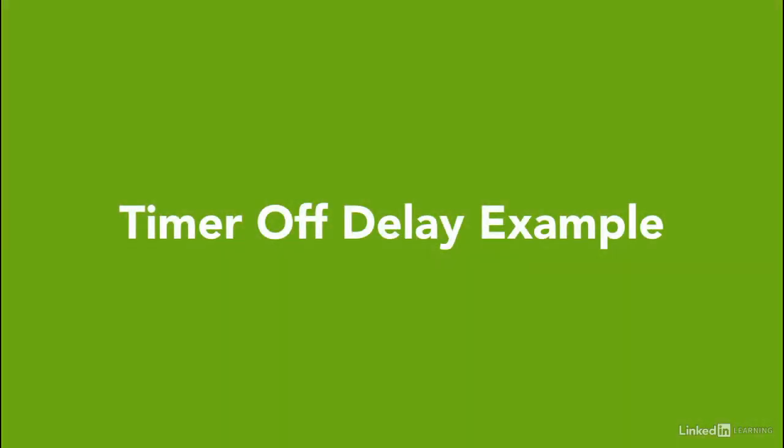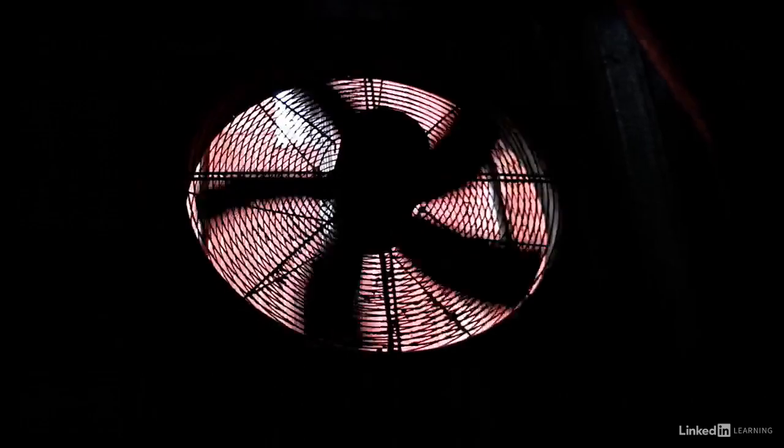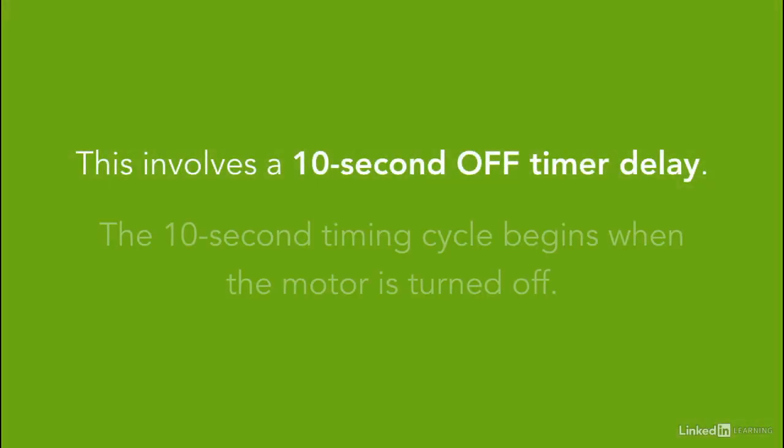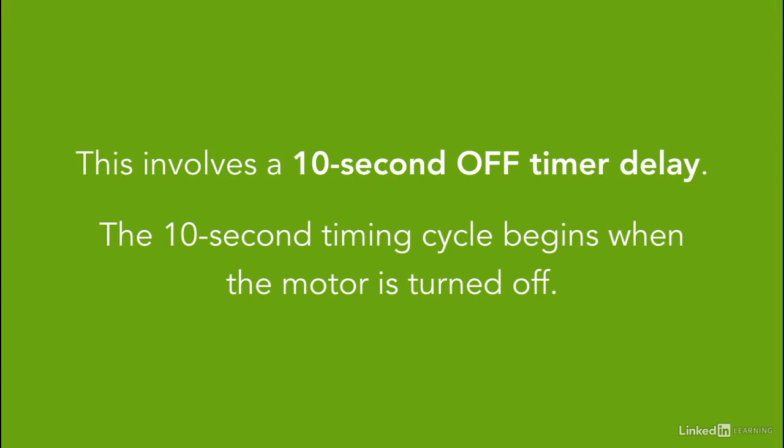So one of the example of using a timer off delay, let's say we have an external cooling fan for a motor is to run all the time the motor is running and for 10 seconds after the motor is turned off. This involves a 10 second off delay timer. The 10 second timer cycle begins when the motor is turned off.